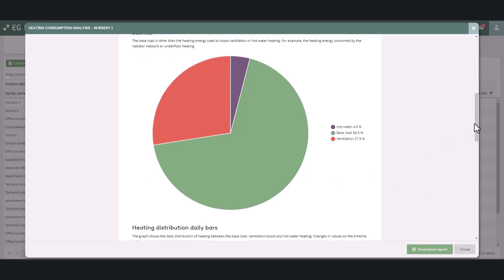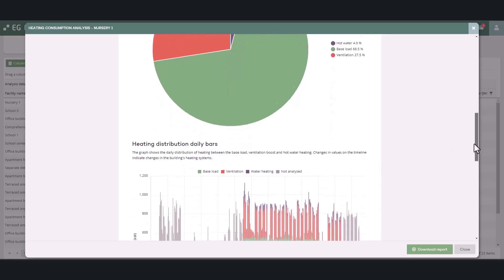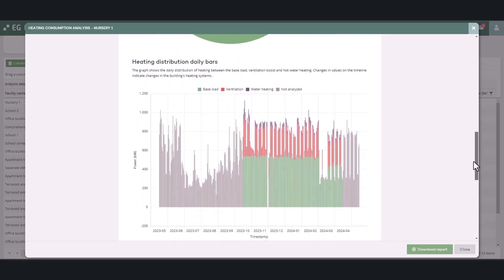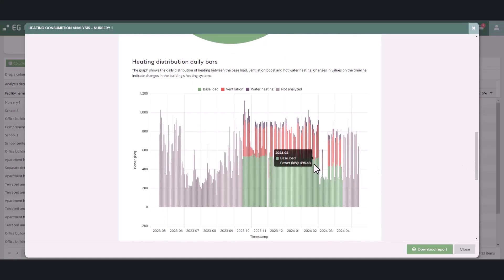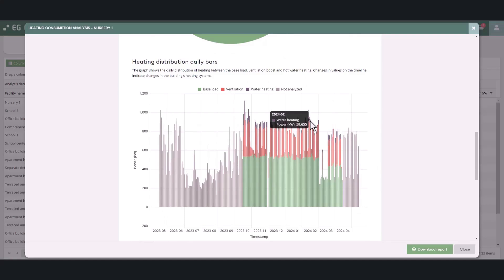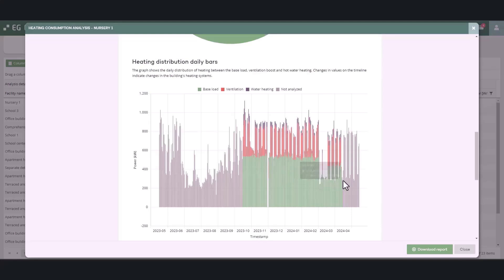In the next graph, you can see the daily distribution of heating consumption. The daily consumptions are normalized to zero degrees to make the results comparable. This allows, for example, detecting if there has been changes in the level of any heating energy component. Changes and adjustments in settings of the heating system can be seen as changes in the level of the base load or ventilation levels.